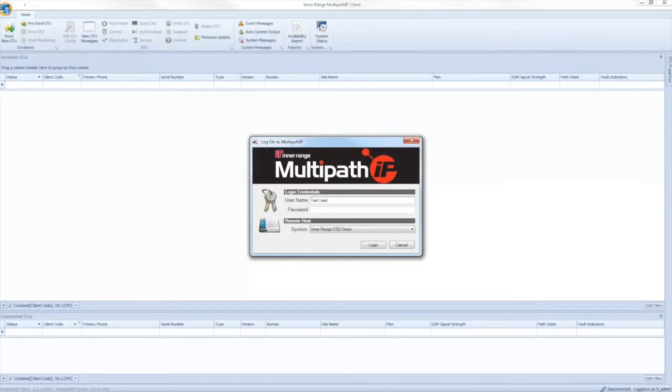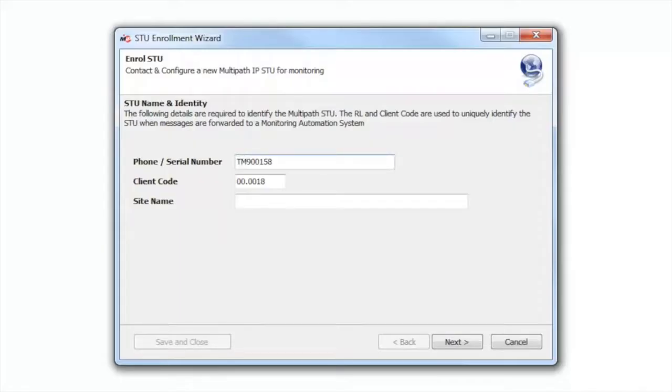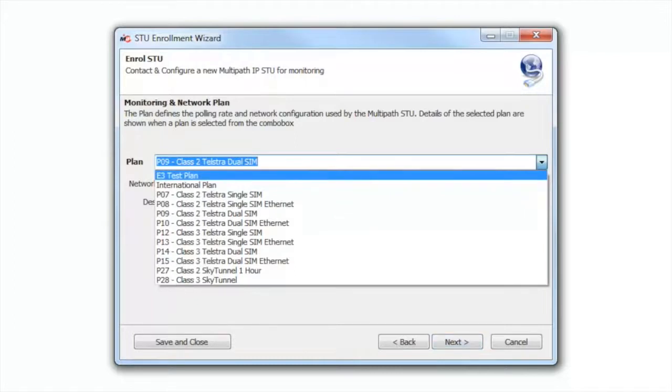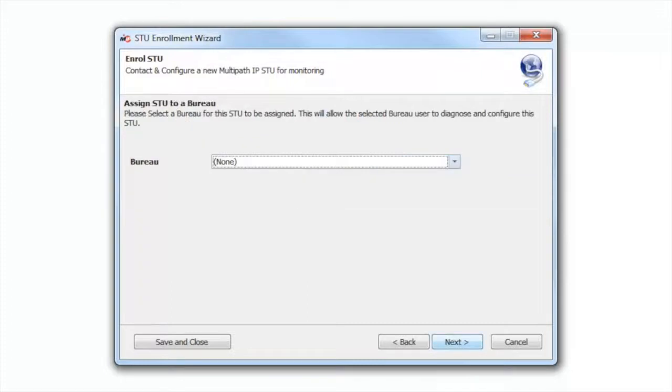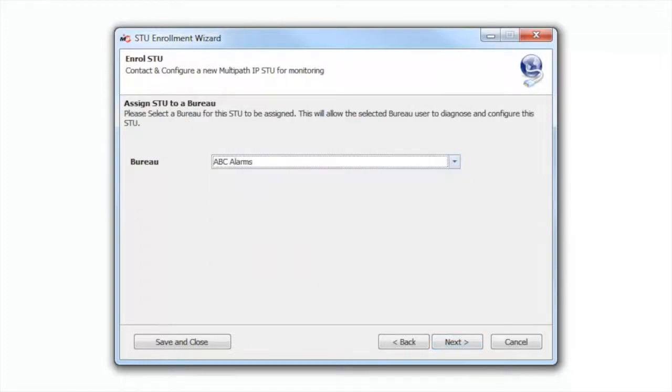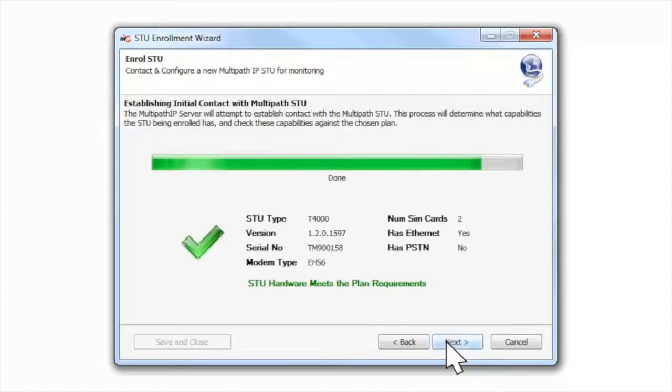First, log in to the Multipath IP client software. Click the enroll new STU icon and enter the T4000's serial number, client code, and site name. Select a plan for this site. The plan will determine the T4000's polling rate and supervision time. Select the bureau that the T4000 belongs to. The system is now fully programming the T4000.